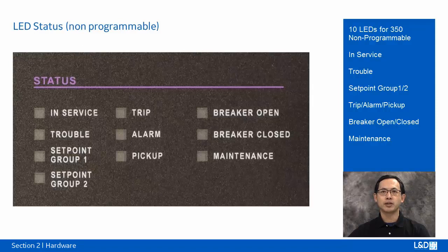Breaker open LED can be programmed to red or green color. When the breaker is open, the indicator will be on continuously. Breaker closed LED is also programmed to red or green color. When the breaker is closed, this indicator will be on continuously.